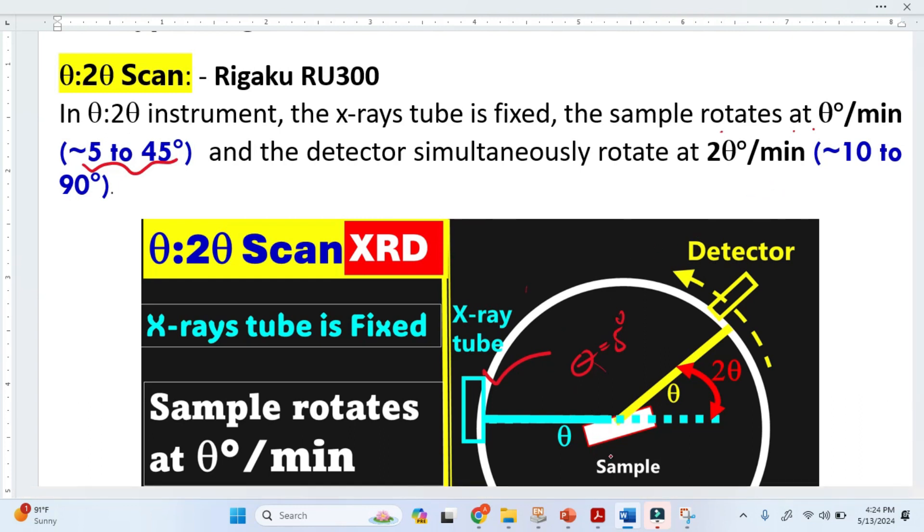In this theta to 2 theta scan arrangement, the X-ray tube is fixed, the sample is rotating, and the detector is also rotating. The sample rotates at theta per minute.